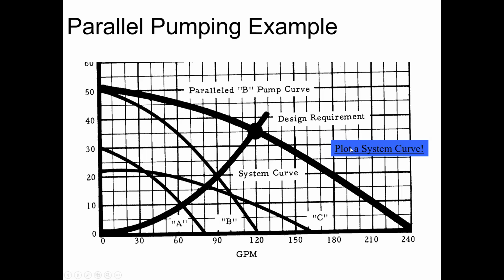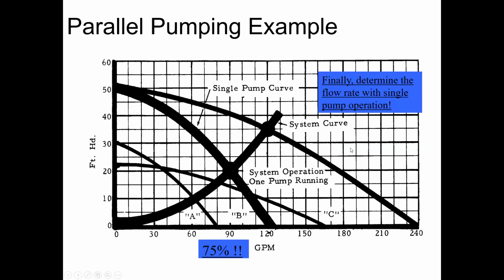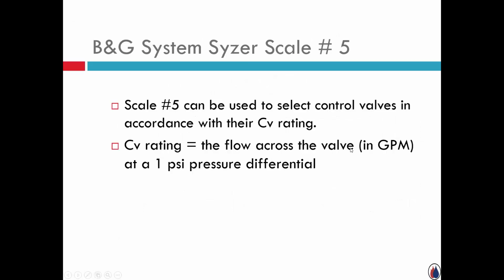So you know that. So then it says, okay, where am I operating with one pump? Well, it's right here. When I look at the flow rate, it's about 90 gallons a minute. That's not 120 and it's not 60, but it's about 75%. So it's just to be aware of that. Sometimes the guys will design parallel pumping for different reasons. Recognize that when one pump shuts off, it can't back up to half. It's going to be something greater than half, but it's not full 120 because it can't be. If that was the case, you would have had one pump. So it's just another example.